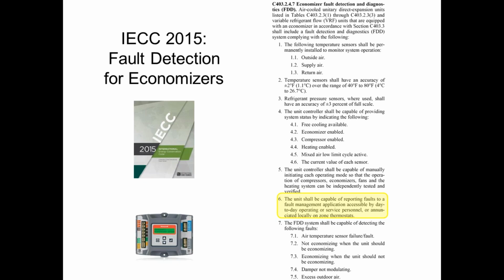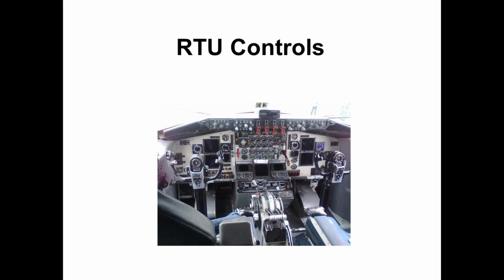These economizer controllers have an auxiliary output they can close when there's an alarm, and some of the thermostat manufacturers have an auxiliary input to receive that alarm. And those thermostats will be labeled on their product literature as FDD input or something like that. Or you can go to the state website. The state website actually has, I think I have it coming up in a few, but I think there's 3 manufacturers they've put on there. We'll talk about that, actually talk about that right now.